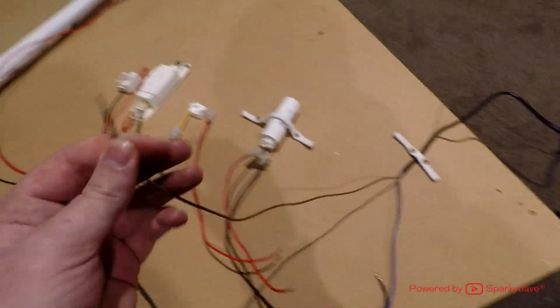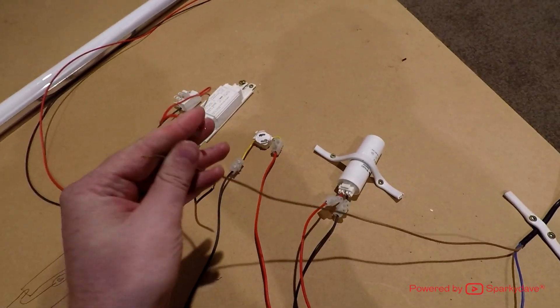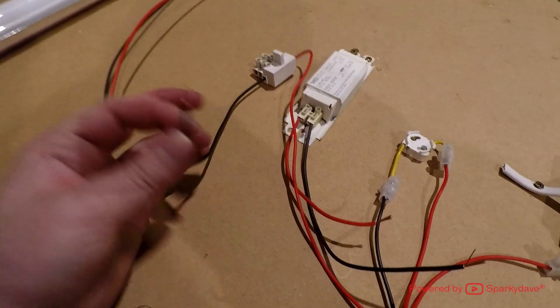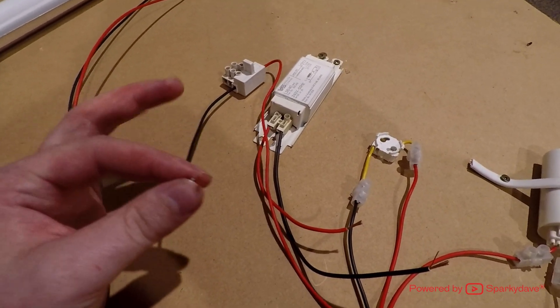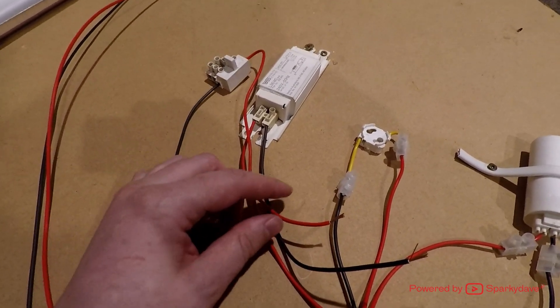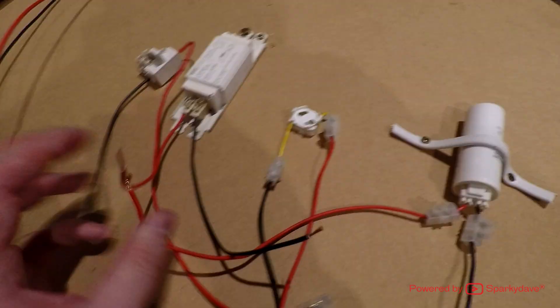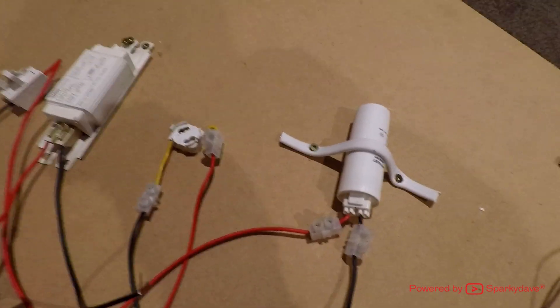This brown cable of the incoming phase will go straight into the red cable of the fuse. Coming out of the black side of the fuse I'm going to tie in the red side of the ballast and the red side of the capacitor together in a connector.